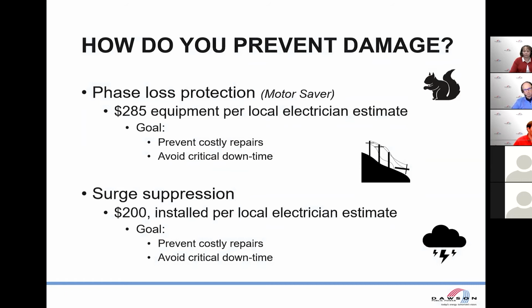As far as the motors themselves go, something called a motor saver, which is a trademark name of a piece of equipment that will protect against under voltage, phase loss, and a variety of other type issues. Not a real costly investment. As we've talked to some local electricians, roughly $200 to $300 will put this piece of protection in. A lot cheaper than replacing a multi-$1,000 motor or control panel.